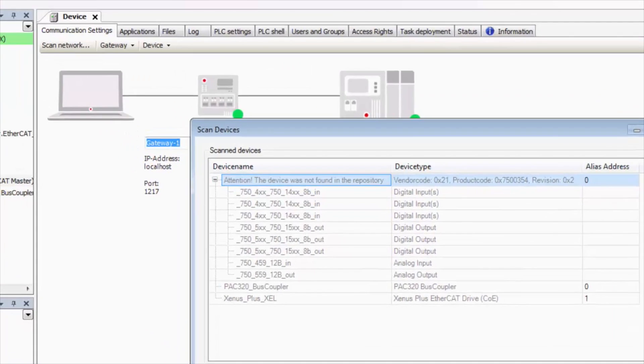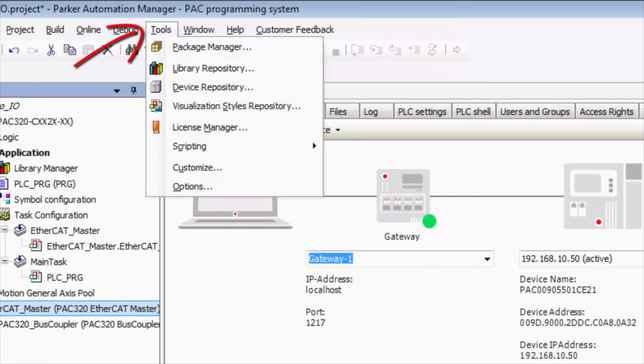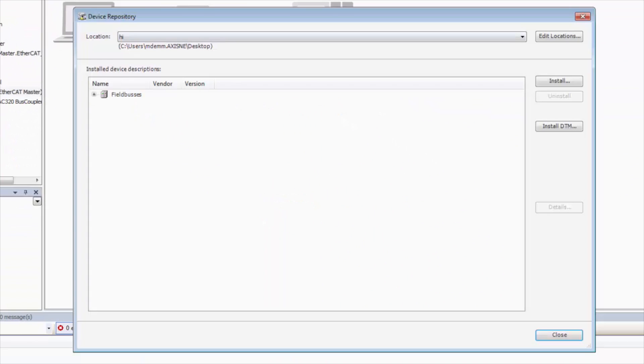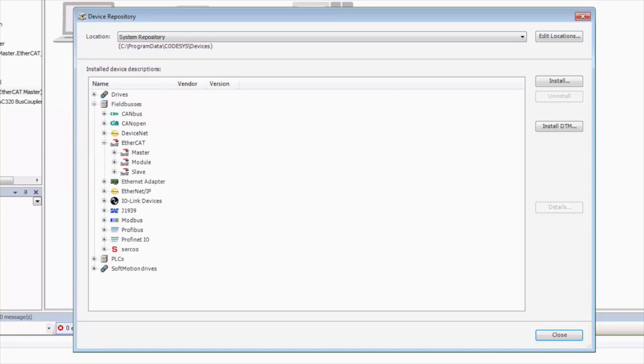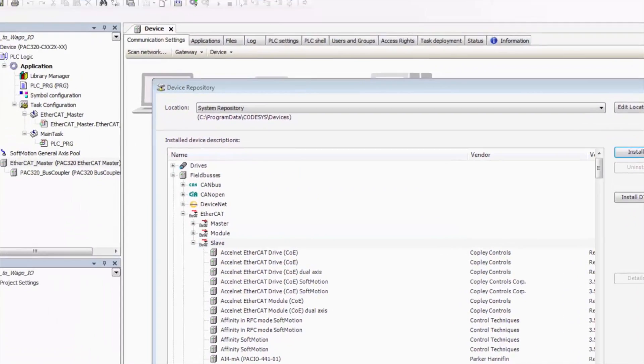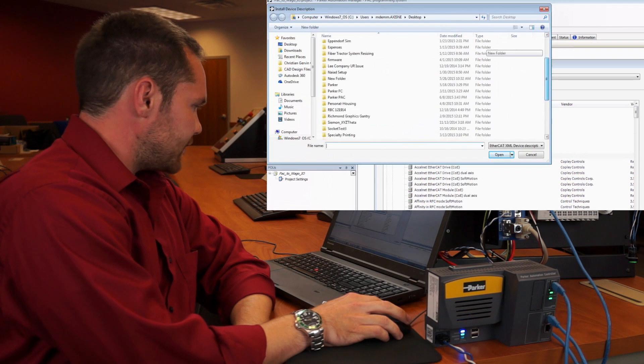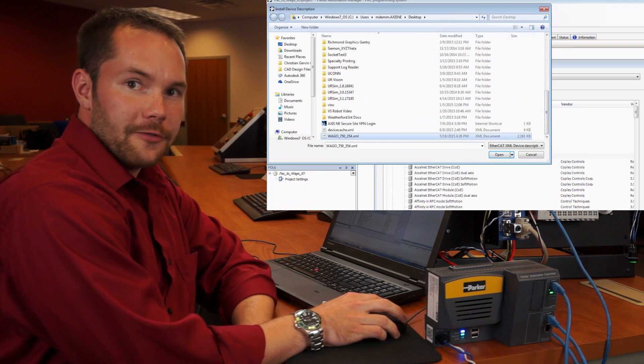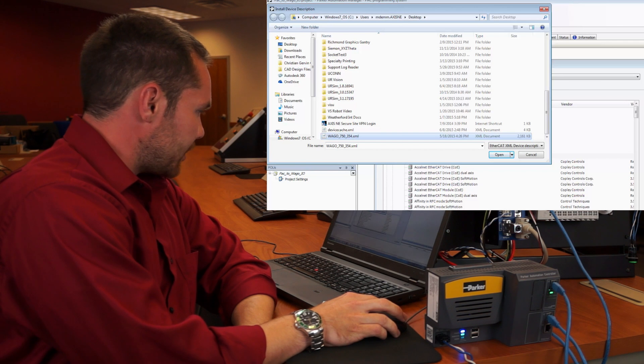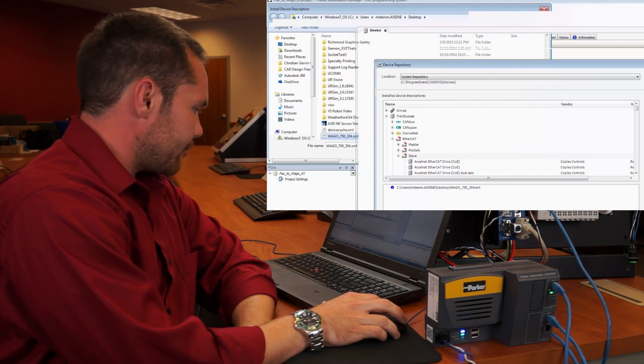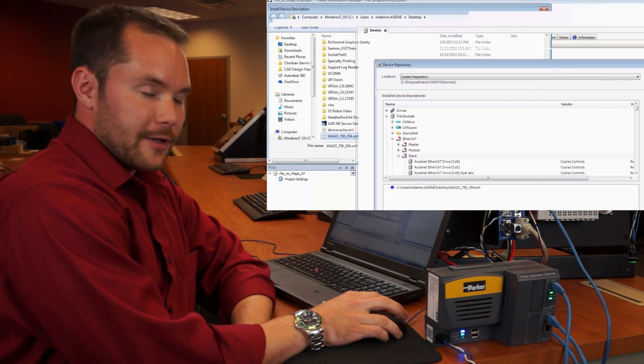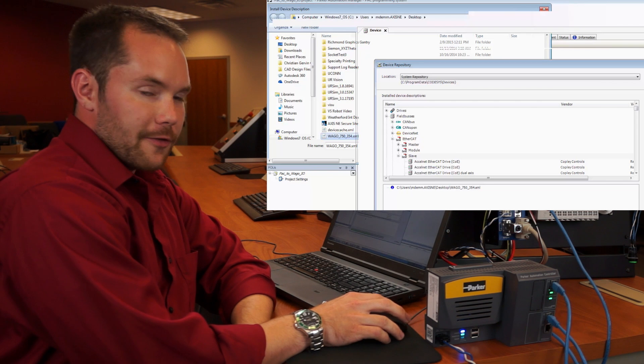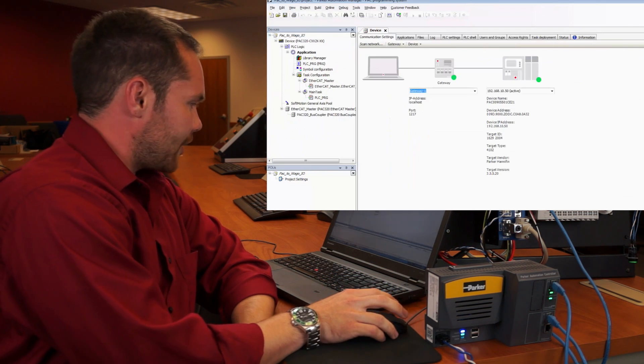In order to get that into our device repository, we go to tools, down to device repository. Then we go to system repository, field buses, EtherCAT, slave, and click install. I downloaded the WAGO EDS file from their website, so all I need to do is double click that and it will automatically install the EtherCAT bus coupler and all of the drivers for the IO modules themselves.